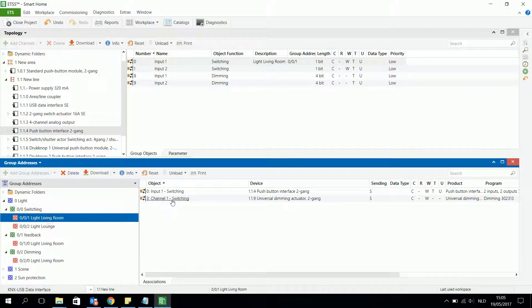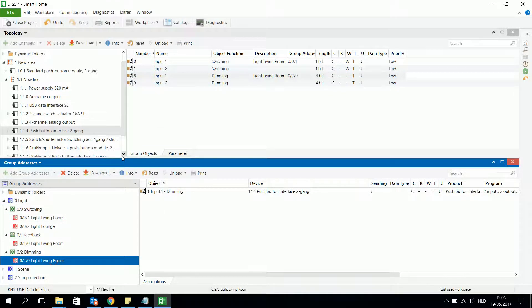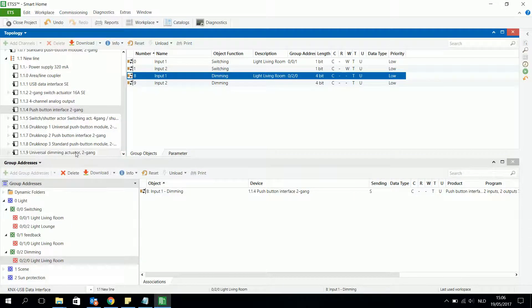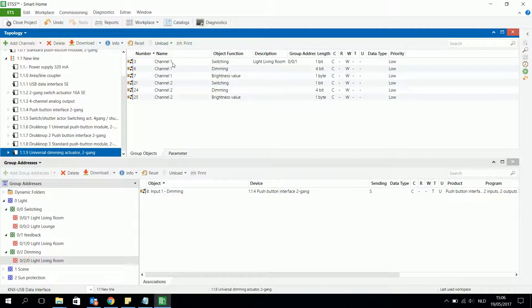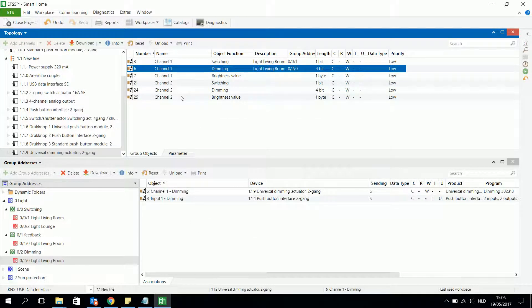I have the switching object of channel 1, and I also need the dimming object of channel 1 of the same bus device. For input 1 of device 1.1.4, I associate the dimming object with the dimming group address. Then on the universal dimming actuator, the same channel also has a dimming object, so I can dim the light connected to channel 1.